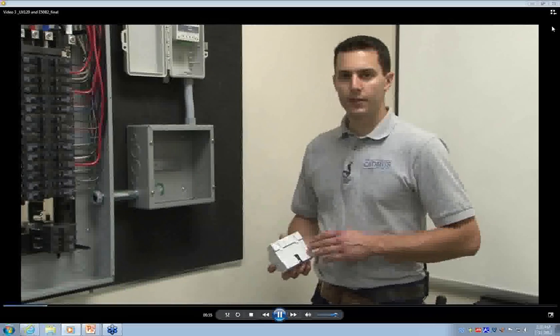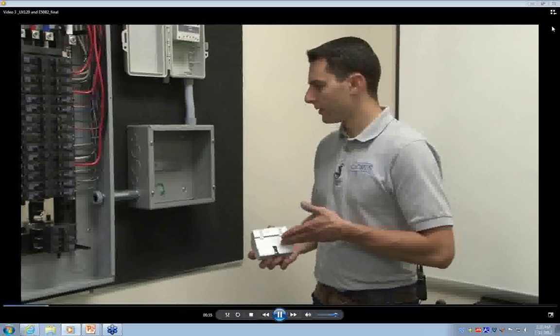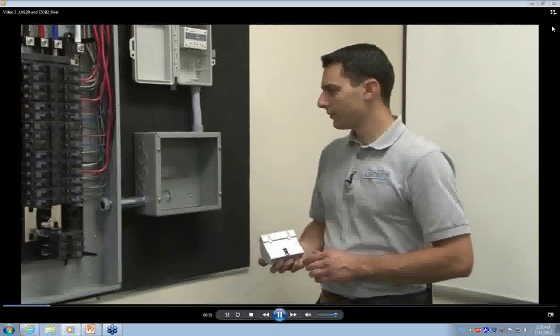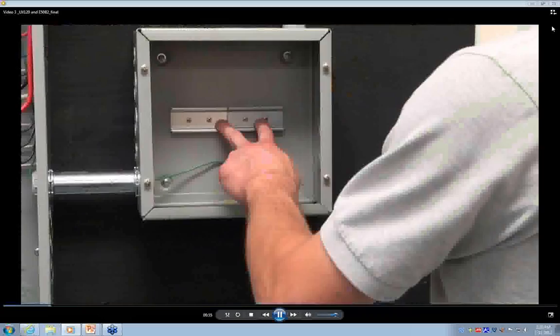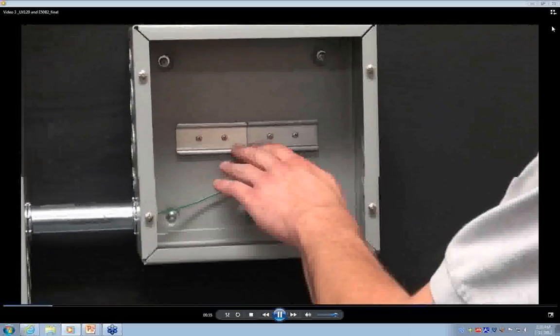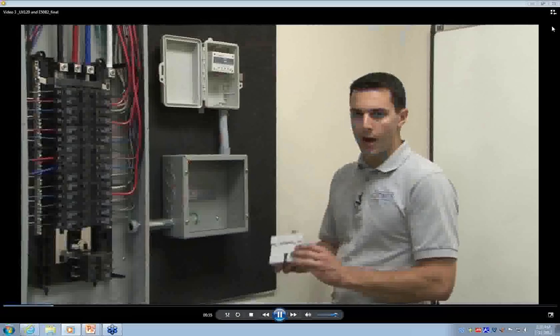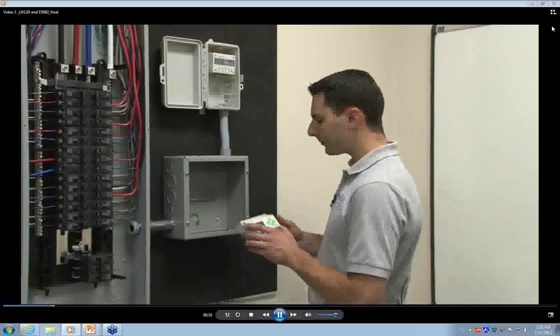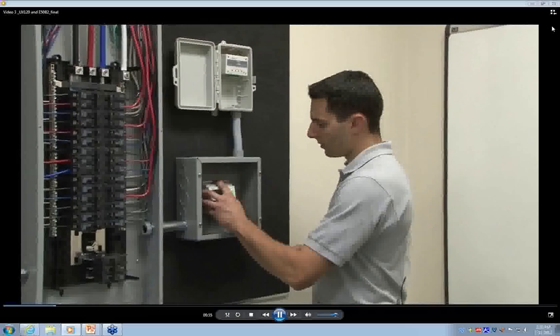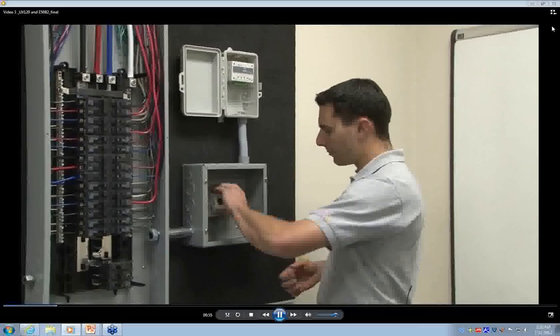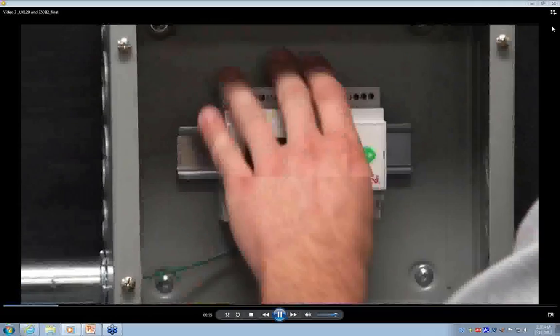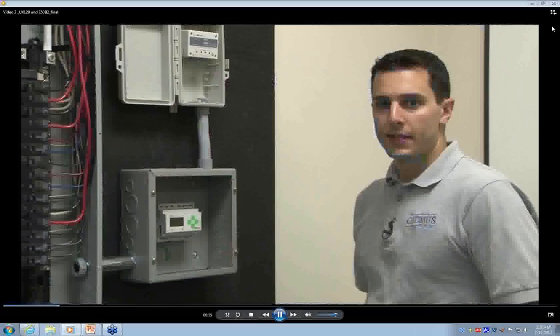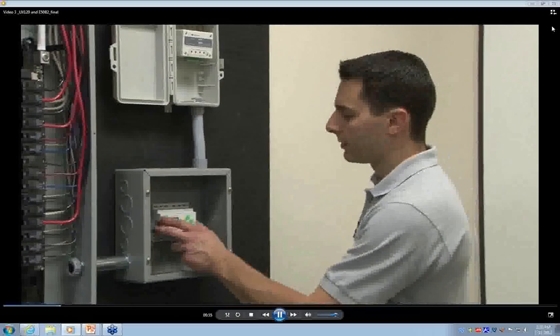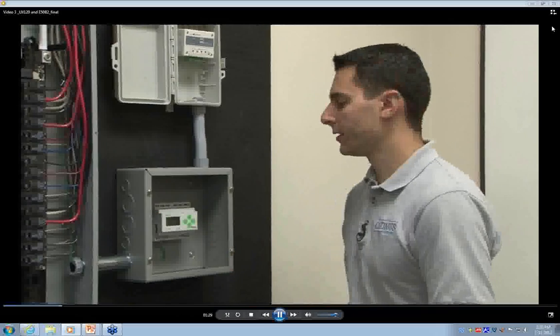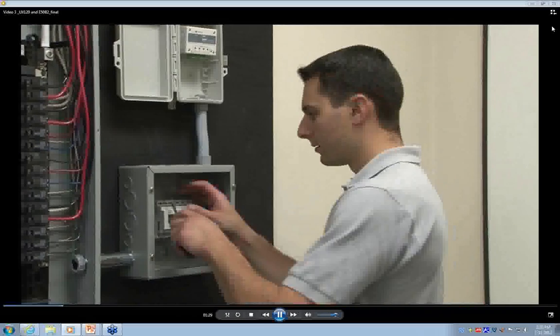The E50B2 power meter will mount directly to the 35mm DIN rail. When we install the DIN rail, it's important that we leave enough room above and below for the wiring to the meter. To install the meter, we connect to the top half and then push down on the bottom half until we hear the click. Now that the E50B2 power meter is in place, we can remove the terminal covers and begin to wire it to the UX120.